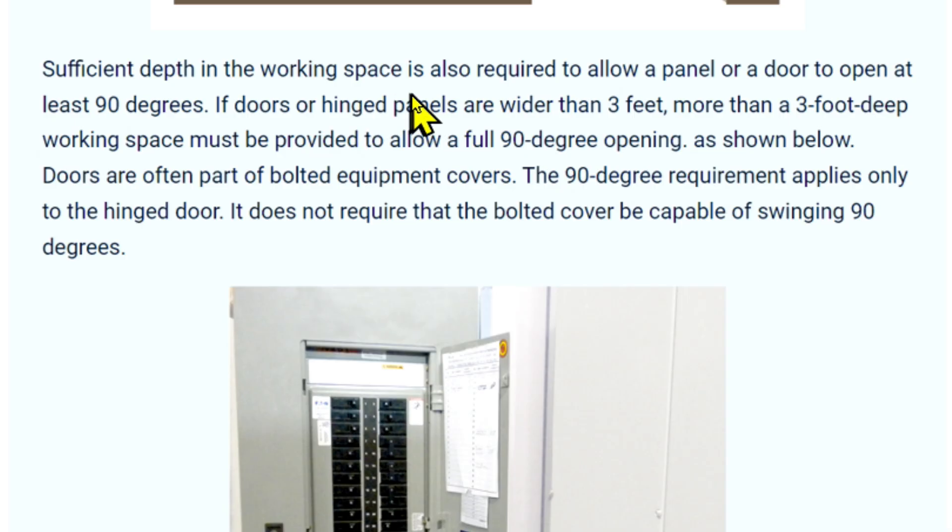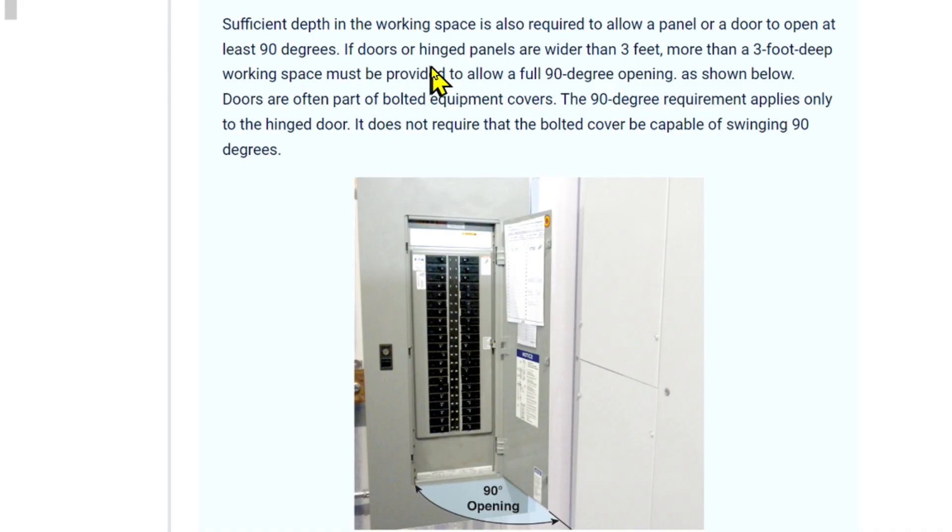Continuing in the 2023 NEC handbook, it says sufficient depth in the working space is also required to allow a panel or a door to open at least 90 degrees. If doors or hinged panels are wider than 3 feet, more than a 3 feet deep working space must be provided to allow a full 90 degree opening as shown below.